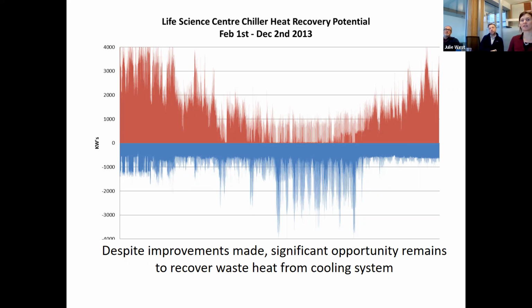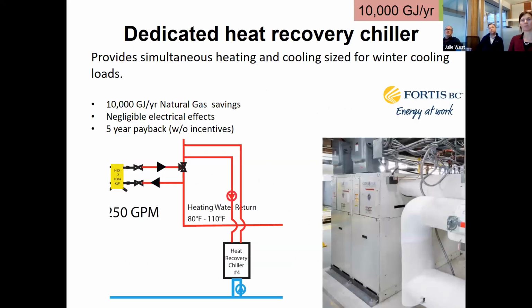So there's roughly 500 kilowatts of base load cooling, and the heating demand around half a megawatt. So we put together a project with help and incentives from our gas provider, FortisBC, to implement a dedicated heat recovery chiller in this building. And so we added, in addition to this HEX, we added a heat recovery chiller to bump up the temperature of the condenser water loop to inject more heat into the supply water, heating water for the building. And this resulted in 10,000 gigajoules of natural gas savings, had fairly negligible electrical effects, and a 5-year payback without incentives.